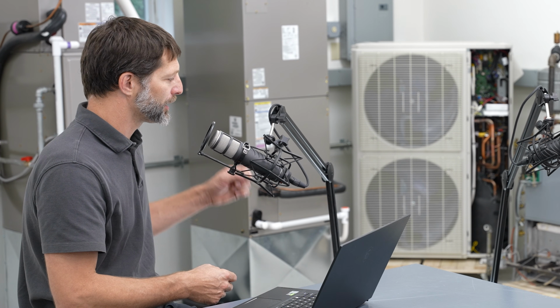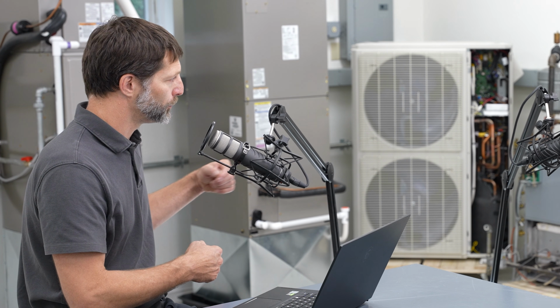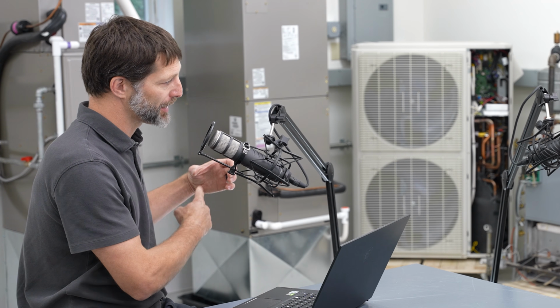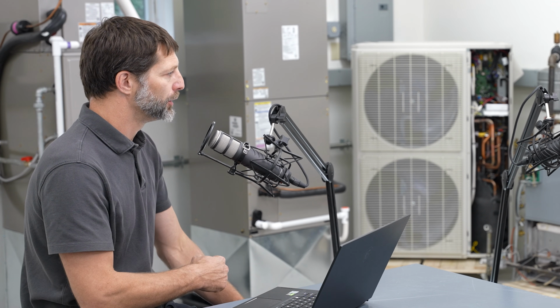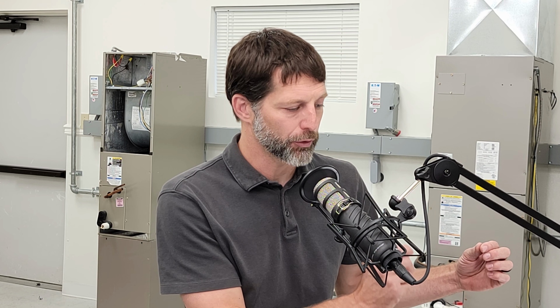And then you're going to have a common over there with that wiring harness or terminal with the high voltage, which is actually for the low voltage. And so what you want to do, if the motor's not running, is see, well, do I even have 24 volts heading to this motor? You can measure that with a multimeter on each of the speed pins. It's simple for the circuit board inside the furnace or air handler. It's just sending a 24-volt signal to the module where it has a circuit board, and it's just waiting for a 24-volt signal on one of the, say, 4 or 5 speed terminals, and not all of them are going to be programmed.